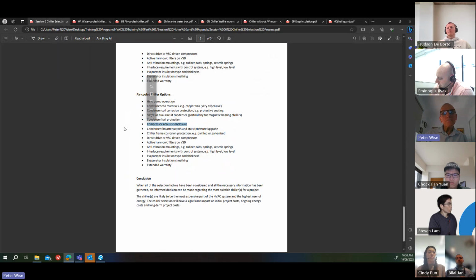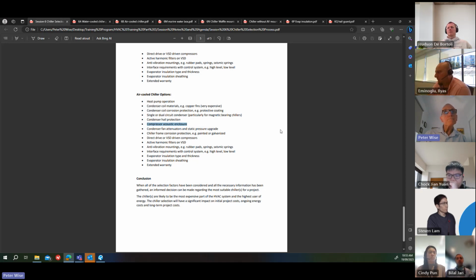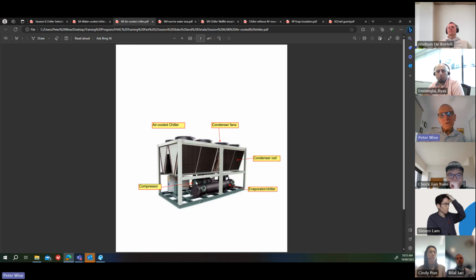Compressor acoustic enclosure, because the chiller is outside. If you've got a noisy compressor, particularly say a screw compressor, might be a bit noisy. You can get an acoustic enclosure from the manufacturers. It's a standard item that they can put on, but it costs money. So if we look at the air-cooled chiller again, here's the compressor here. It's just like a jacket that goes around the compressor to reduce the noise level.